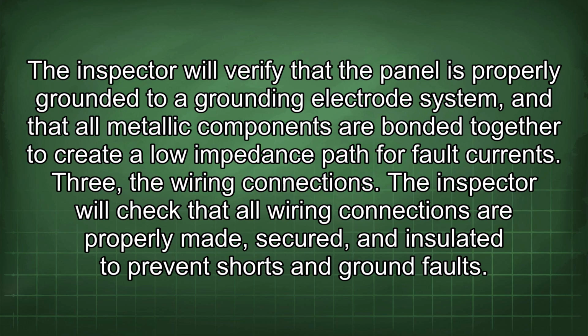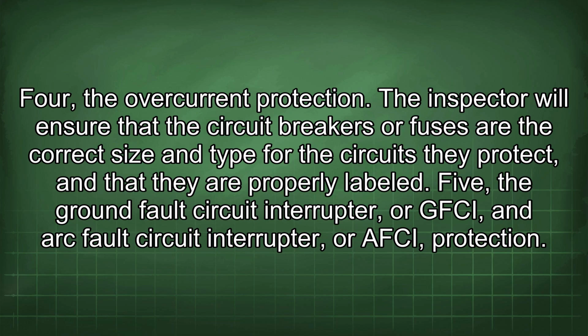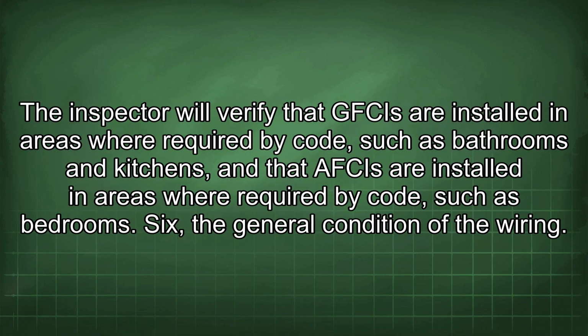3. The wiring connections. The inspector will check that all wiring connections are properly made, secured, and insulated to prevent shorts and ground faults. 4. The overcurrent protection. The inspector will ensure that the circuit breakers or fuses are the correct size and type for the circuits they protect, and that they are properly labeled. 5. The ground fault circuit interrupter, or GFCI, and arc fault circuit interrupter, or AFCI, protection. The inspector will verify that GFCIs are installed in areas where required by code, such as bathrooms and kitchens, and that AFCIs are installed in areas where required by code, such as bedrooms. 6. The general condition of the wiring.